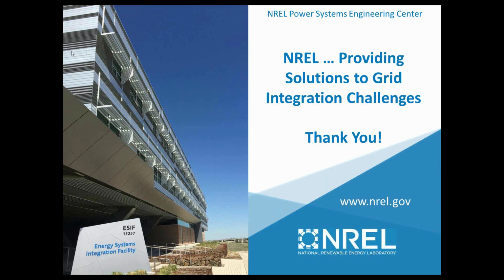But you have to think not only of a variety of sizes, say 20 megawatts, 5 megawatts, 1 megawatt, all the way down to, are you requiring direct transfer trip on every 3 kilowatt PV system that gets installed? It would probably be better to have a consistent method that addresses people's concerns, and you're probably not going to run DTT to all those different types of examples. So it's something that the industry desperately needs, a low-cost method to ensure unintentional islanding requirements are met.